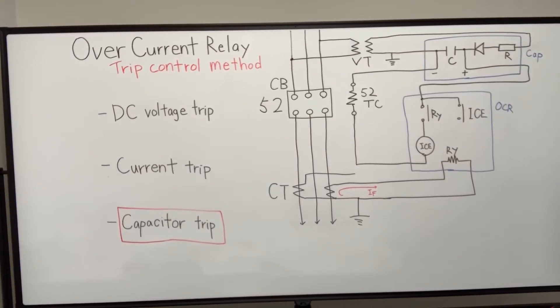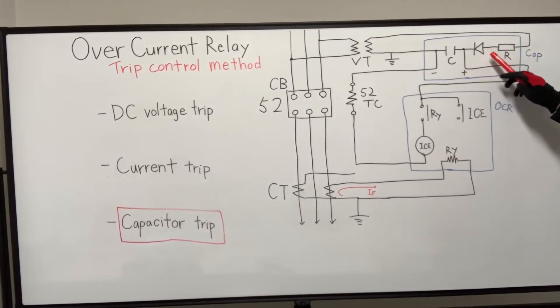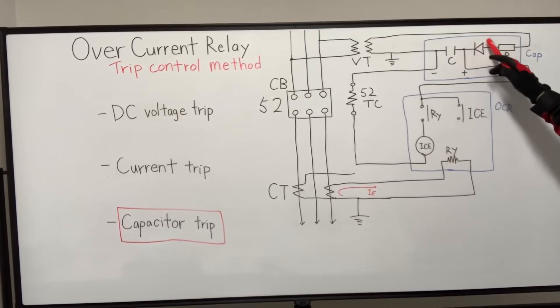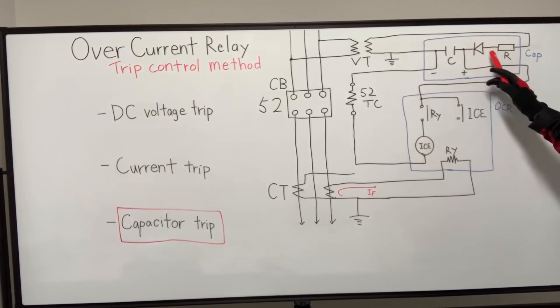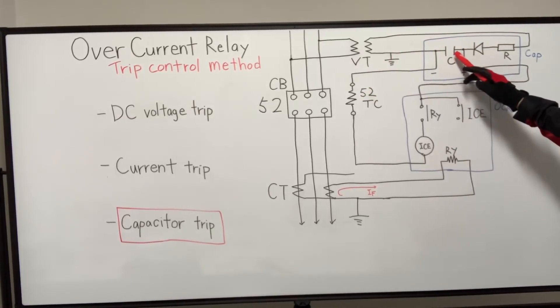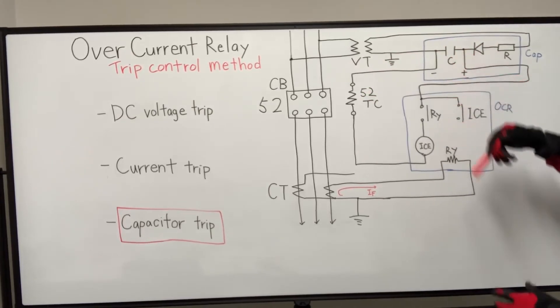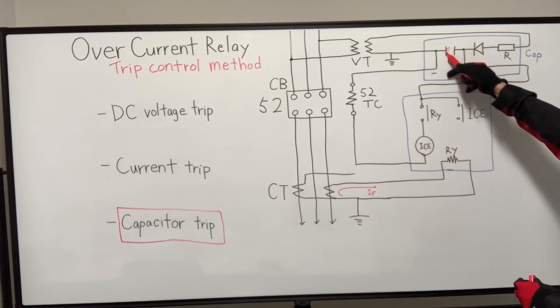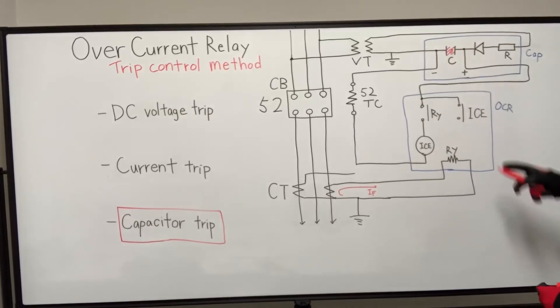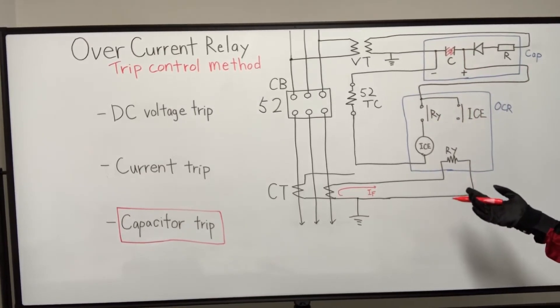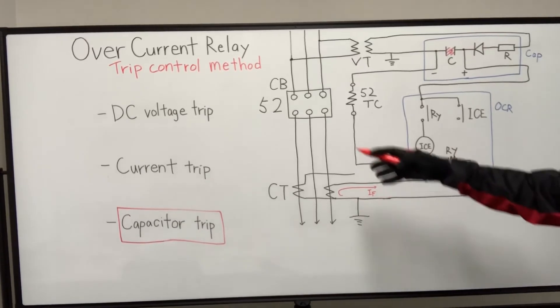The last one is capacitor trip. In this manner, there are diode and capacitor in the house. And the diode can rectificate AC to DC. Power system AC to control circuit DC. And DC is charged in this capacitor. And trip coil will be energized by using this charge. Other than that, it's the same principle as DC voltage trip.